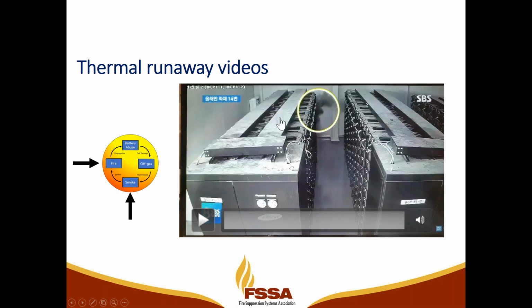Now, one point that I will point out here is if we're using early warning smoke detection, much like we would see in, say, a data center where you have a cold aisle configuration and a hot aisle configuration, and you have cooling from the back of the rack to the front of the rack, we'll want to look for external factors of early warning detection. So fire that's outside of the battery or cells or modules themselves could provide an external abuse factor.